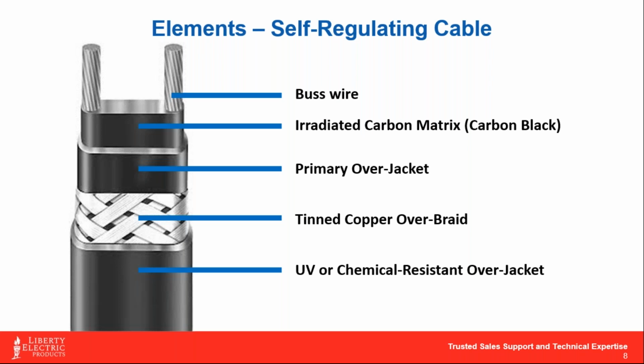Okay, so it's kind of important to note, when you get into the designing portion of this, that you're not taking that wattage output for granted, let's say. The tinned copper over-braid was added to heat cables probably about 5 to 10 years after they were originally incepted in the 60s. And this helps with a means for grounding. You can basically twist up that tinned copper over-braid and terminate that on the grounding screw, and that becomes your means of ground.